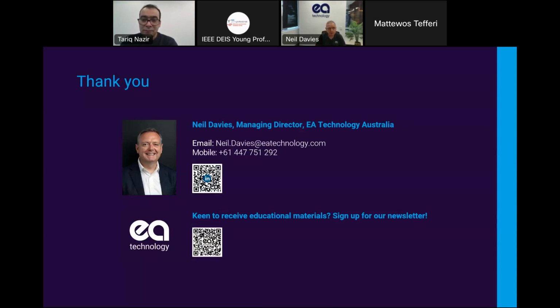Good question. Maybe. Not necessarily, actually. If it's a wet cable, and it depends if it's an XLPE cable, a wet cable that causes water trees, the water trees will typically go to electrical trees before failure. But again, will you get any massive warning on that? The answer is probably no. It'll be a very fast failure mode.